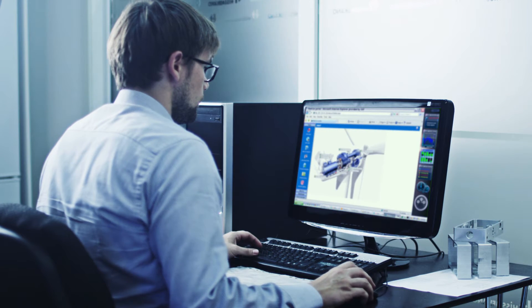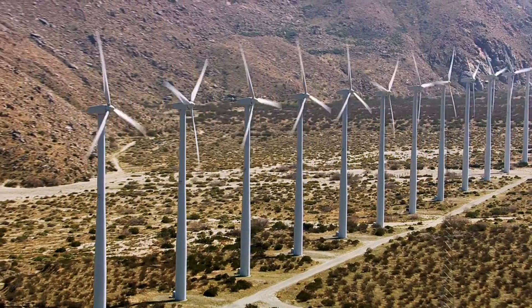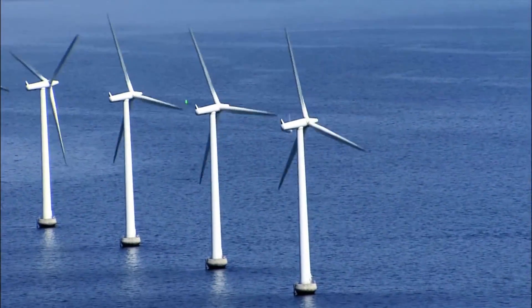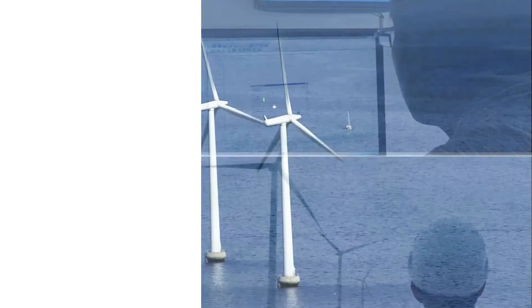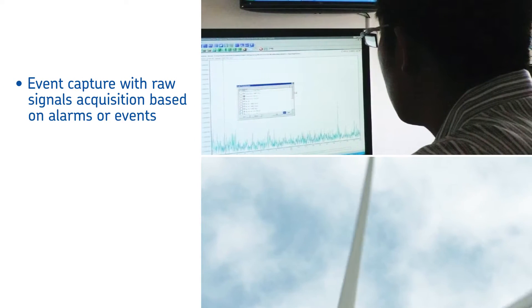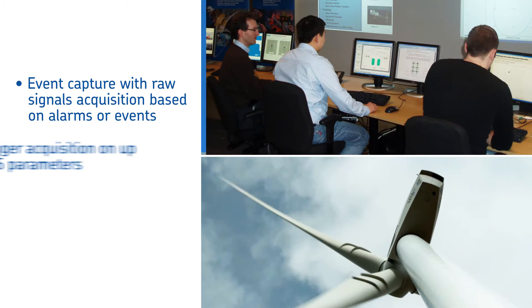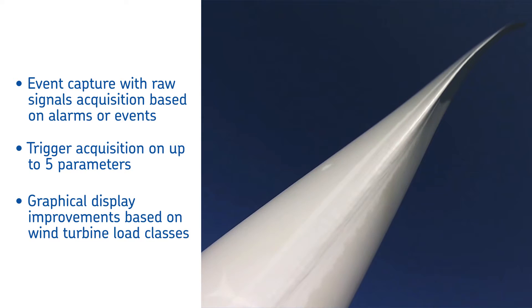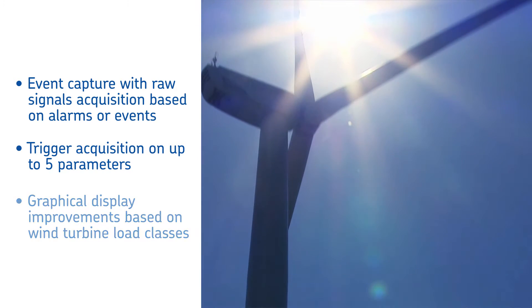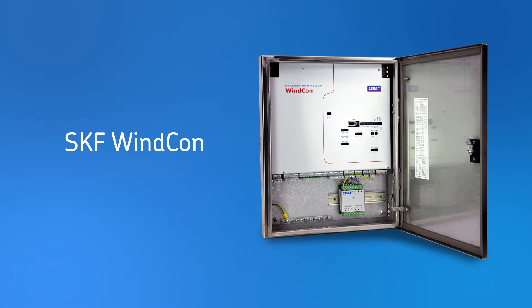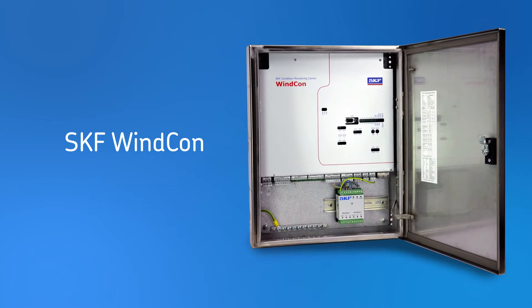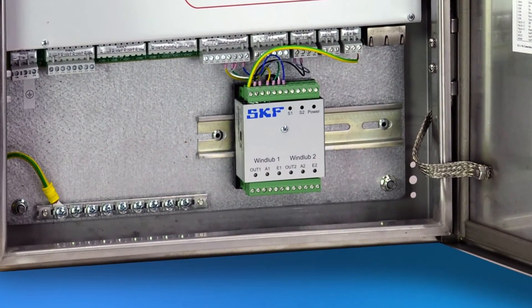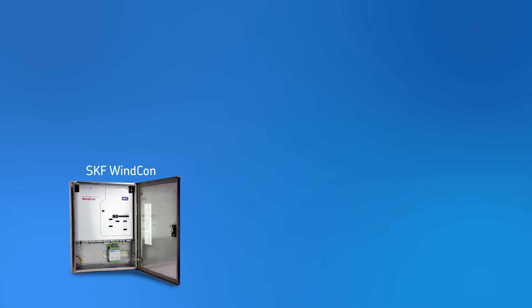Our updated SKF Aptitude Observer software makes turbine service even more efficient with many new features, including event capture with raw signals acquisition based on alarms or events, trigger acquisition on up to five parameters, and graphical display improvements based on wind turbine load classes. The SKF Windcon system also includes an RS485 Modbus, which can be used to transfer measurement data to the Windcon unit from other systems.